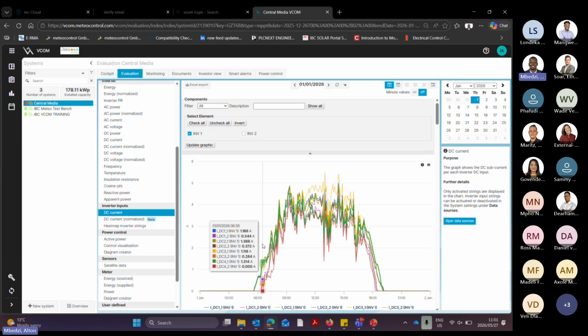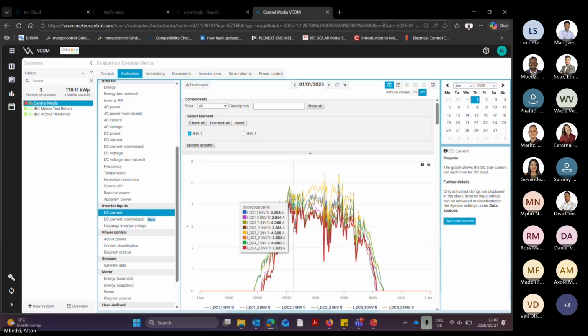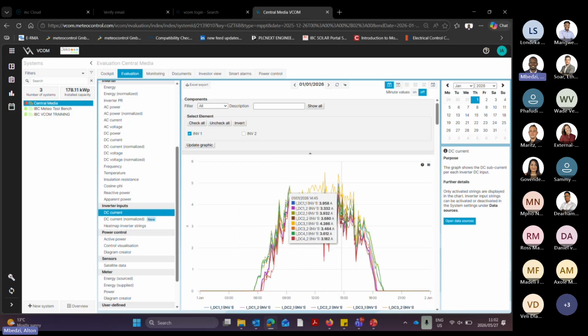Here you'll see the DC current. Depending on the inverter you have, you can rename each string on VCOM as built, then you'll be able to see the current per string, as you see there on inverter number 1, or per MPPT tracker. I can see everything is okay, so your fault finding skills are quite sharpened if you use VCOM.